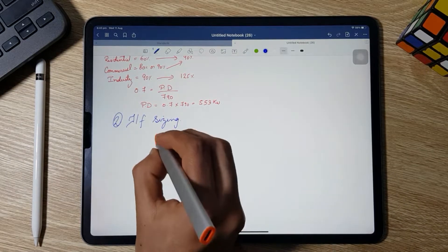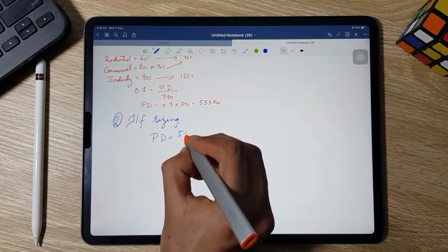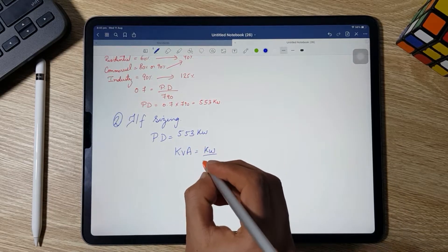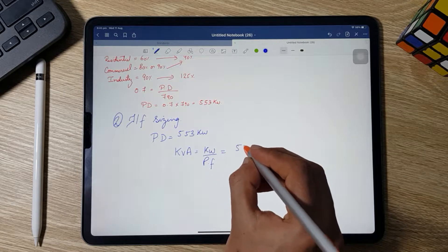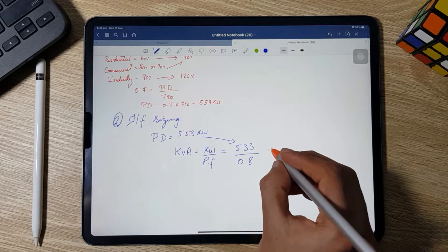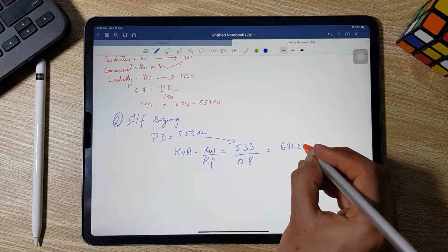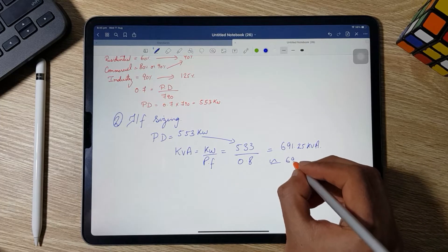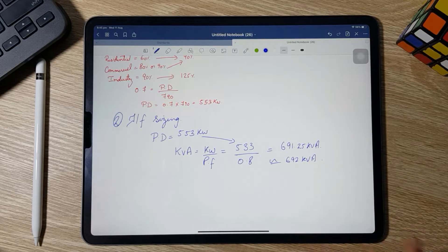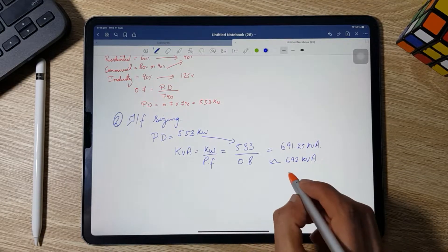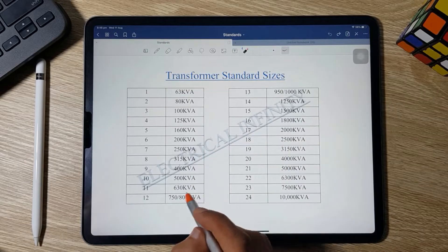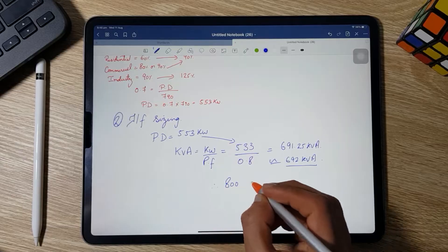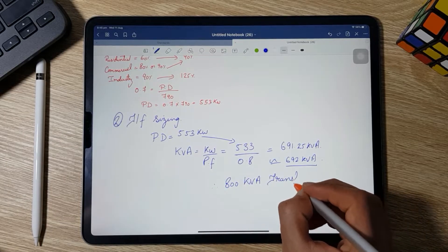Moving to Step 2 — transformer sizing. Peak demand is 553 kW. The formula is kVA = kW ÷ power factor. Substituting 553 kW and a power factor of 0.8, we get 691.25 kVA, approximately 692 kVA. Referring to standard transformer sizes, we select an 800 kVA transformer for our building.